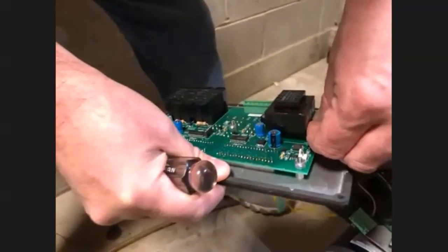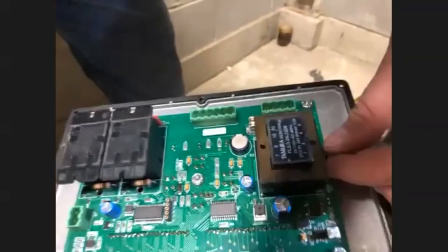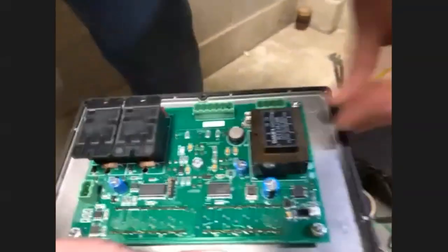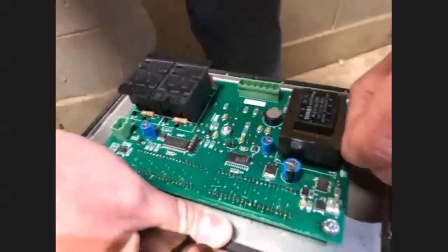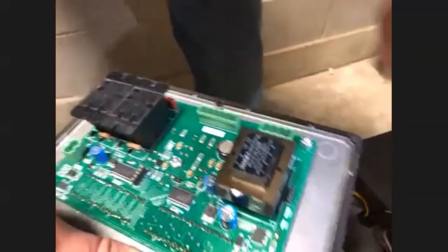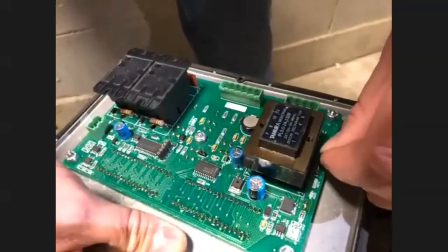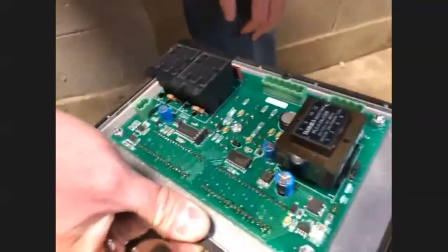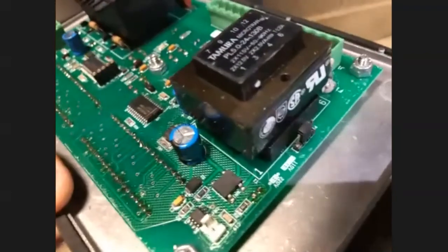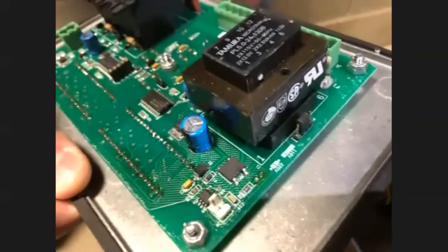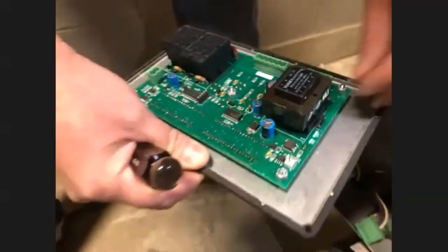I would remove both the jumpers. They're set on separate terminals. To set it for 230, I'd take one jumper and put it on the two middle terminals. Now it's set up for 230 volt. Very simple to do.